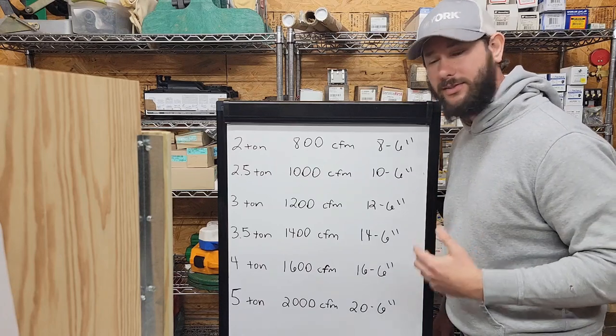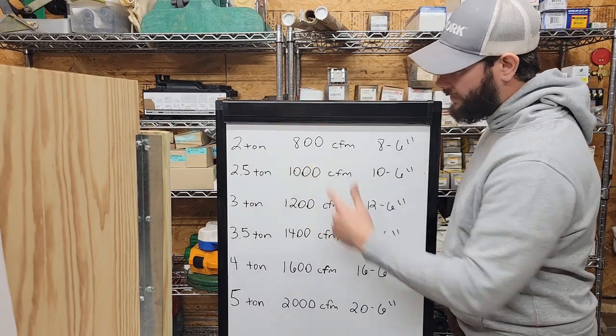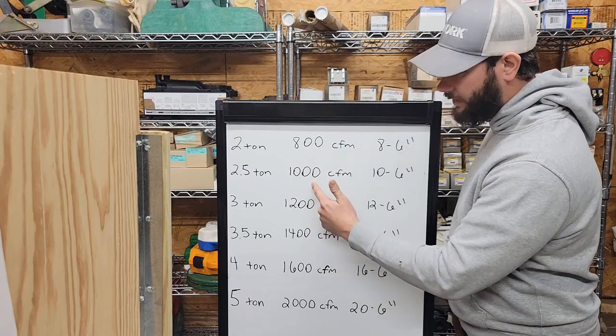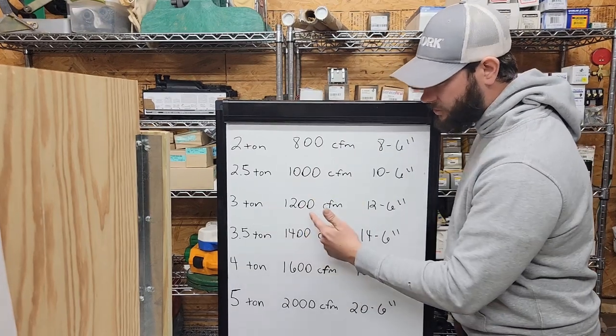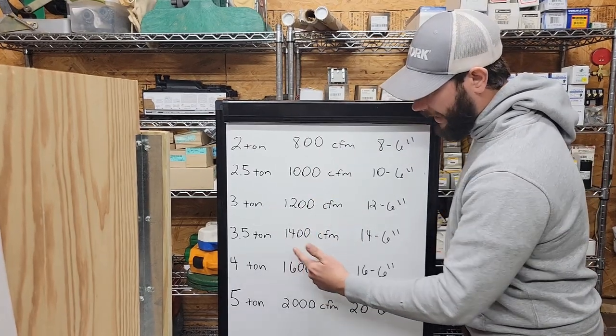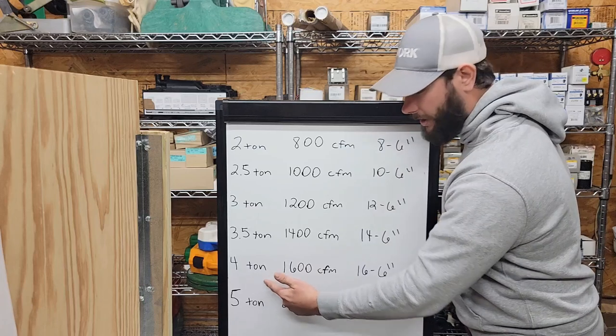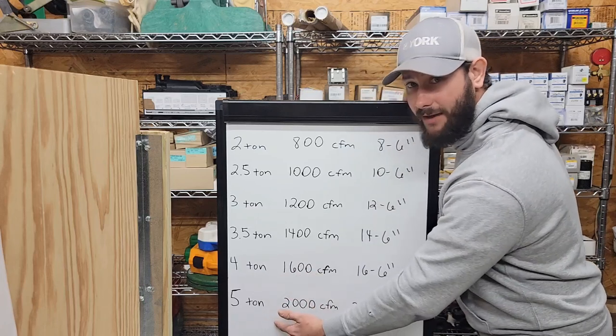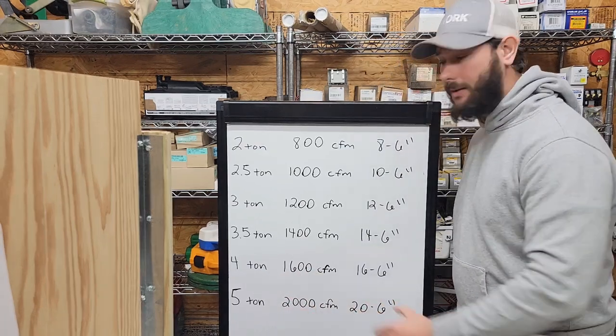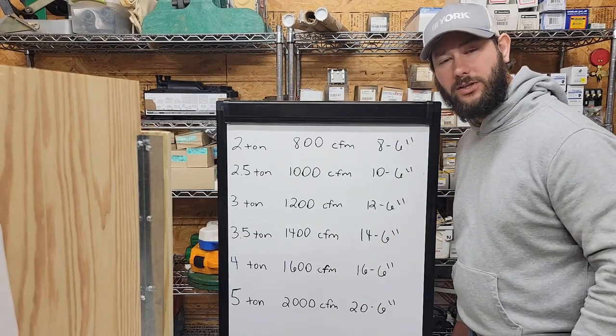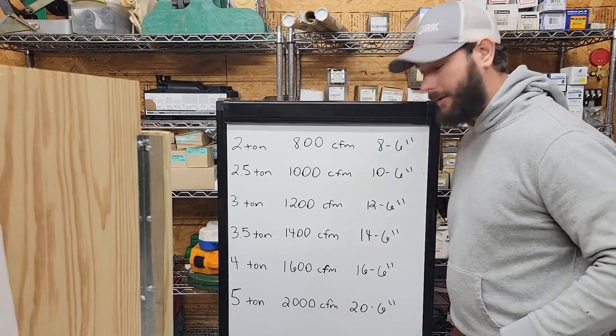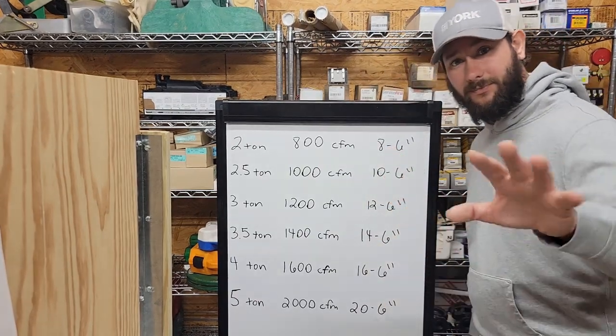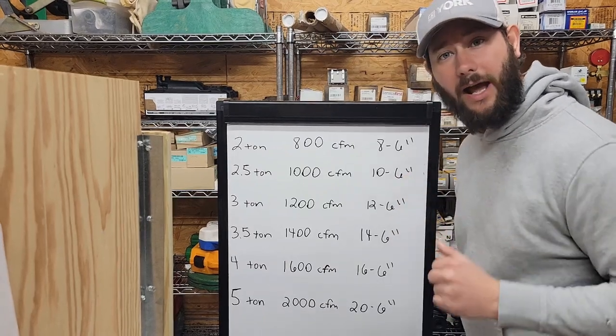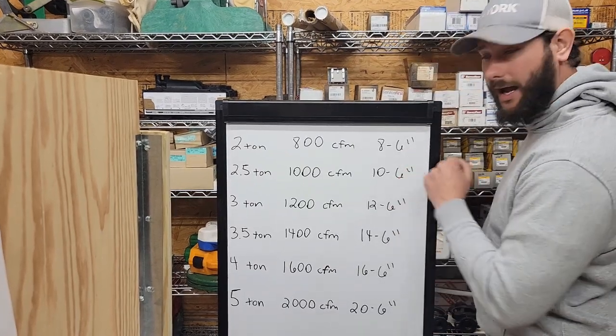all those branch ducts. So, 2-ton, 800 CFM; 2.5-ton, 1,000 CFM; 3-ton, 1,200; 3.5, 1,400; 4-ton, 1,600; and 5-ton, 2,000 CFM. Memorize this because you're going to take this with you to all your jobs from now on. Beside this is what I expect to have for lines.